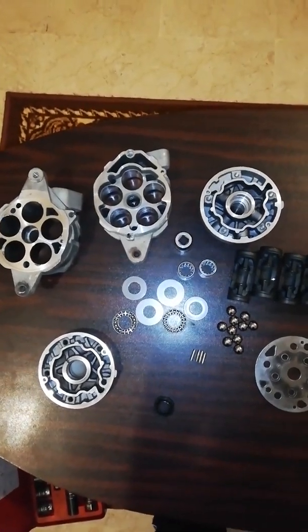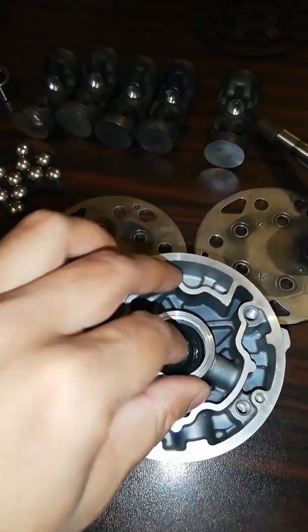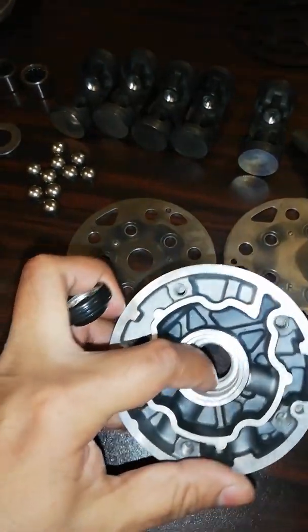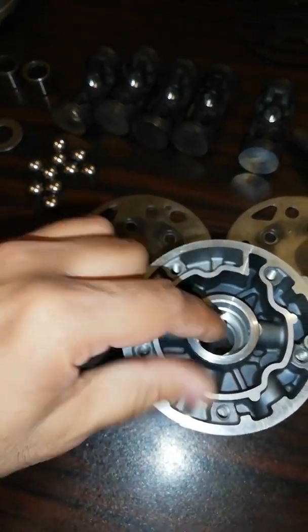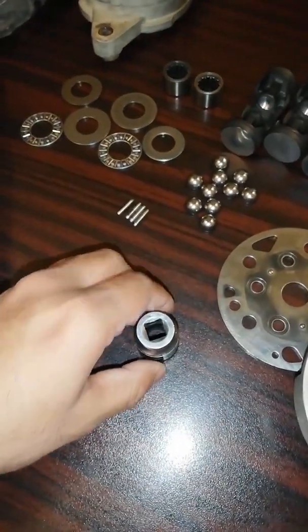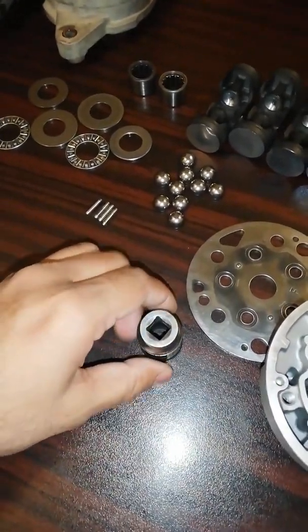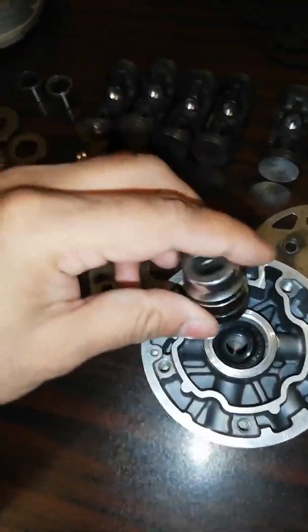The first step is the fitting of the lip seal in the front body of the compressor. This is the front end of the compressor, and this is the lip seal. There is a groove inside the body where the seal is fitted. Select a socket that is nearly the same diameter as the outside of the seal — this will not harm your seal — and settle it with light hammering.